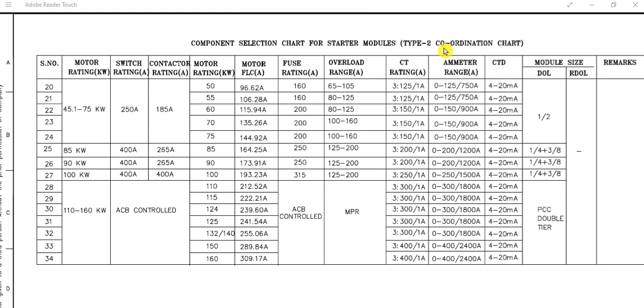So based on their recommendation, we need to select the components, that means the switch rating, contactor rating, fuse rating, overload selection range, current transformer, ammeter range, and current transducer. So once again I will brief for this. Suppose for the 75 kilowatt motor, the full load current is coming 144.92 ampere, almost 145 ampere. So here we need to select the fuse rating as 200 ampere. This is recommended by the panel supplier.